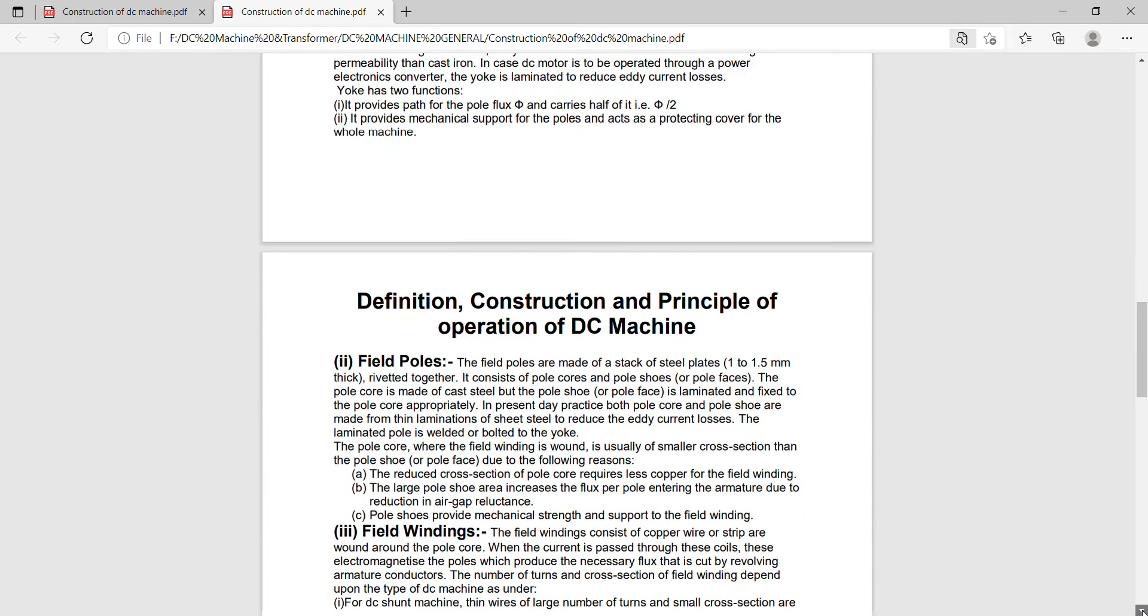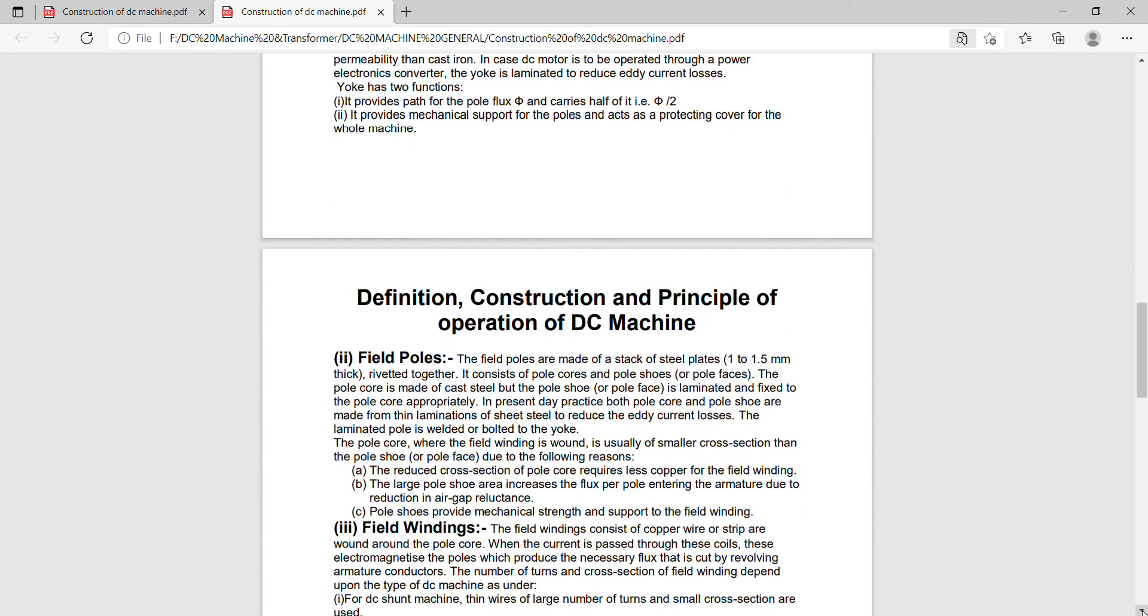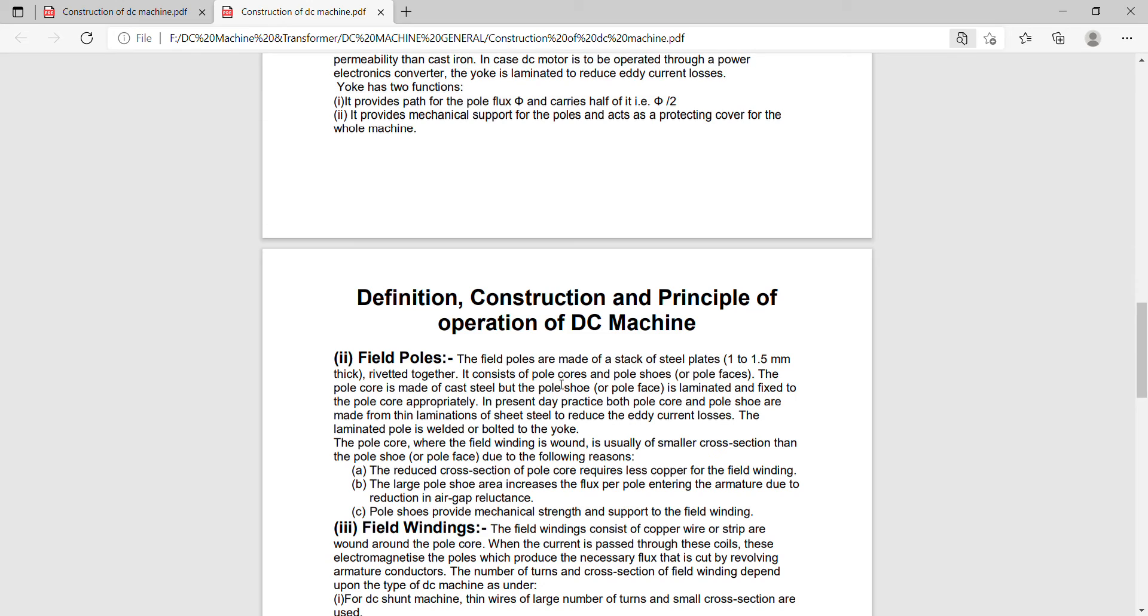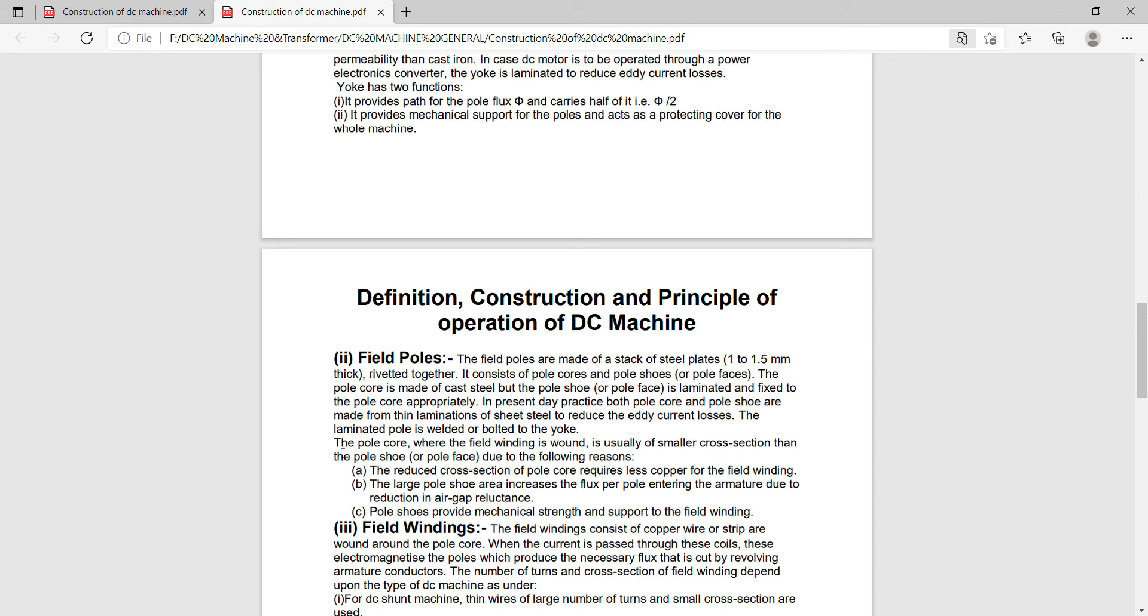Field poles. The field poles are made of a stack of steel plates, 1 to 1.5 mm thick, riveted together. It consists of pole cores and pole shoes. The pole core is made of cast steel but the pole shoe or pole face is laminated and fixed to the pole cores appropriately.